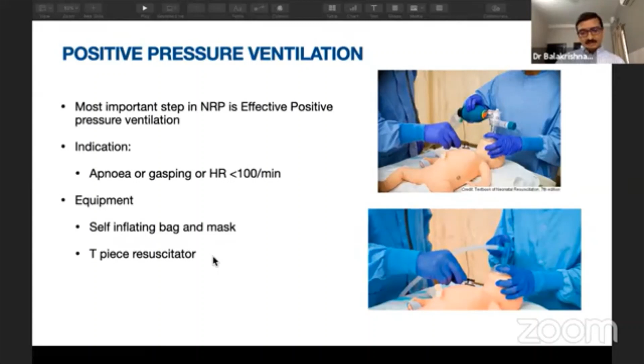So the alternative is the T-piece resuscitator. The advantage of the T-piece resuscitator is we are able to give PEEP and we're able to decide the PIP that needs to be delivered to the baby. But the disadvantage is it's expensive and we need a compressed source of gas to run the T-piece resuscitator.